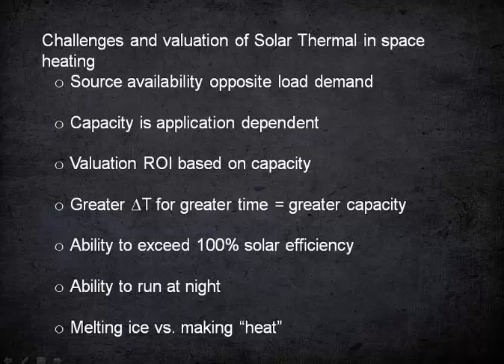It's very interesting when you fire up a solar collector drain-back tank at around 35 degrees outside, with pure water and no glycol, depending on how you pipe it. My particular system has no glycol in it, just pure water. The first time that happened I was a little nervous, but it's been running three seasons now and I've never had a problem. It's interesting to see happen.